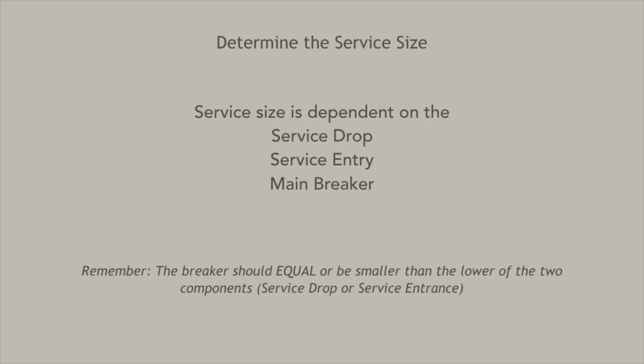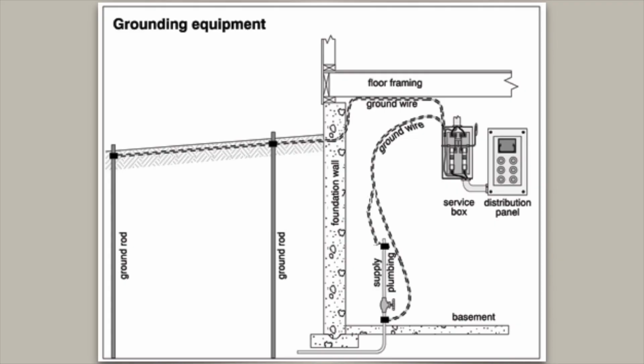Remember, the breaker should equal or be smaller than the lower of the two components, the service drop or service entrance. Standard practices today recommend 2 sources of ground. Typically, we find a ground wire clamped to the city water entrance. A common second source would be a ground rod. Sometimes, there may be 2 ground rods when the water is supplied from a private well. These 2 ground rods must be located further than 6 feet apart.